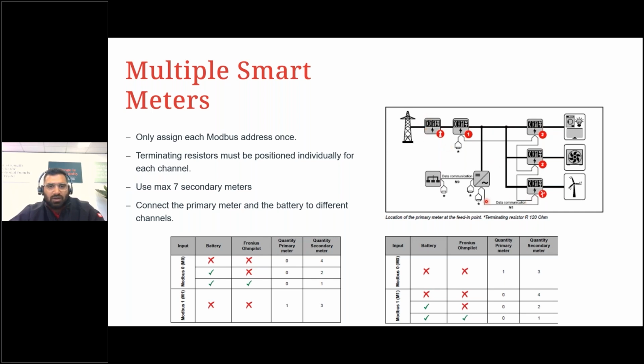So here we are going from the meter in series to the first meter, which is used as a generator meter to monitor a wind turbine. And we have 2 meters monitoring a specific load path. And then you have a primary meter, which is set at the feeding point. So the end of this Modbus line here is the inverter and the primary meter. Hence, we have the terminating resistors on the last meter, which is the primary meter. And by default, it is also active on the inverter.